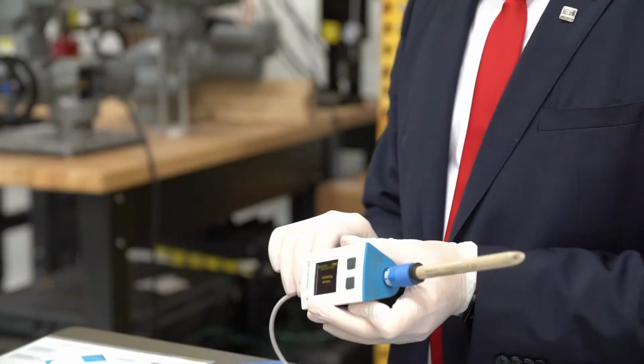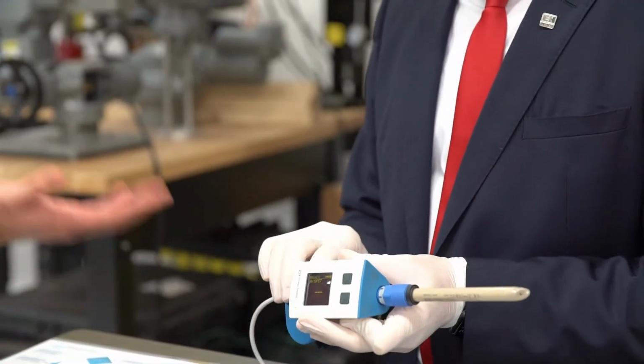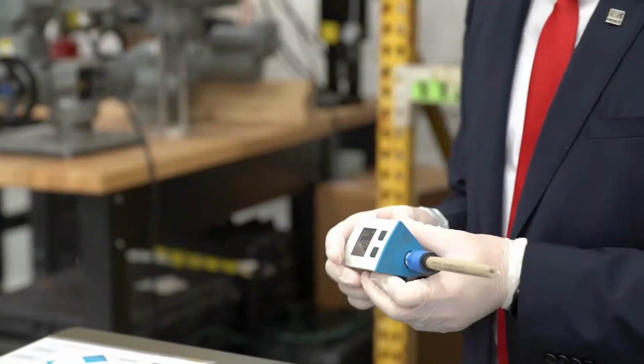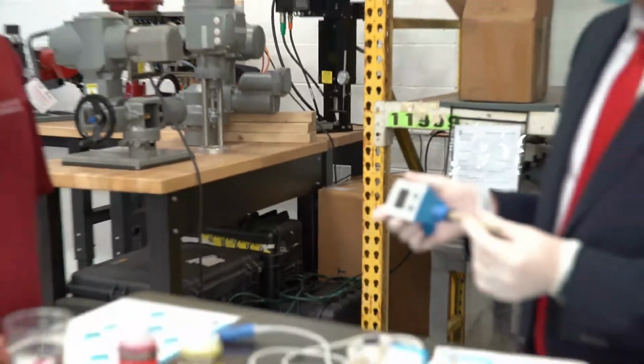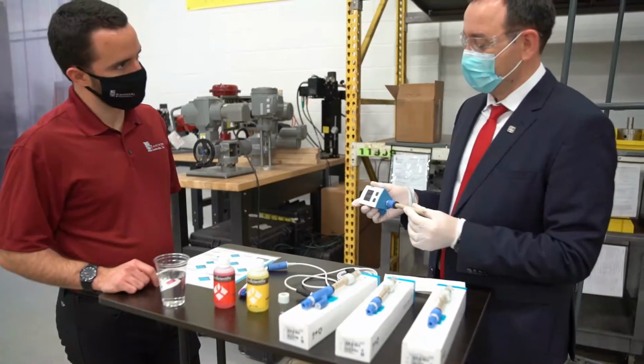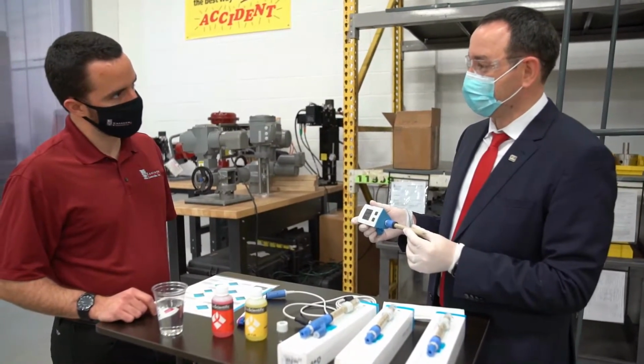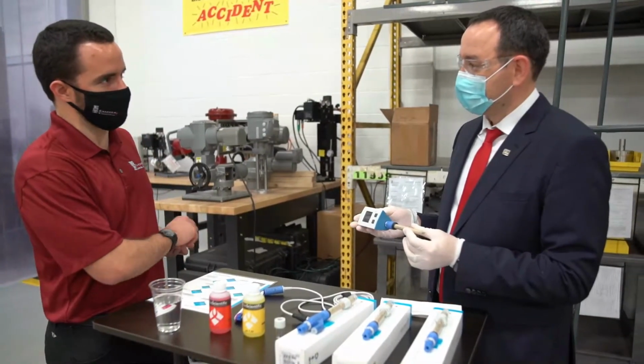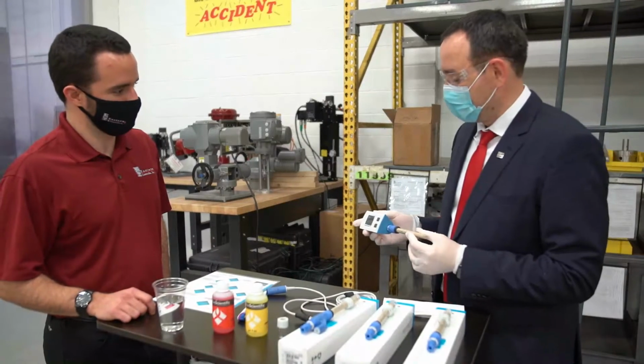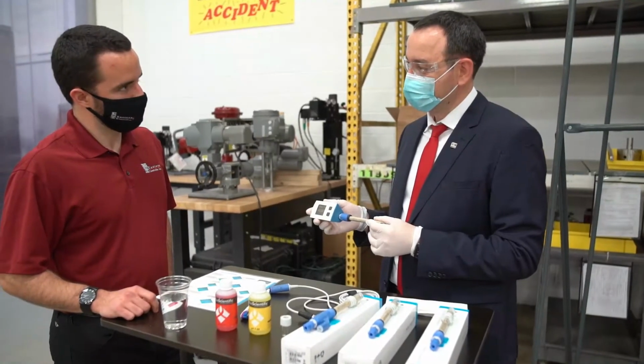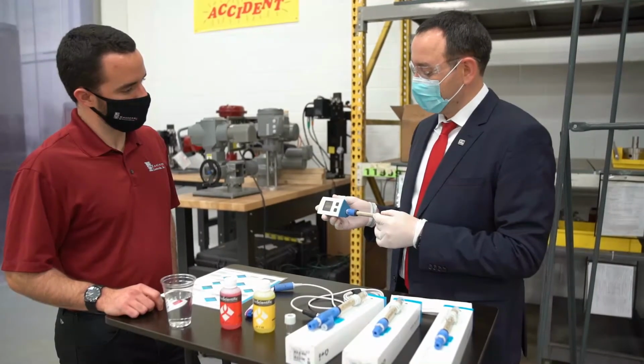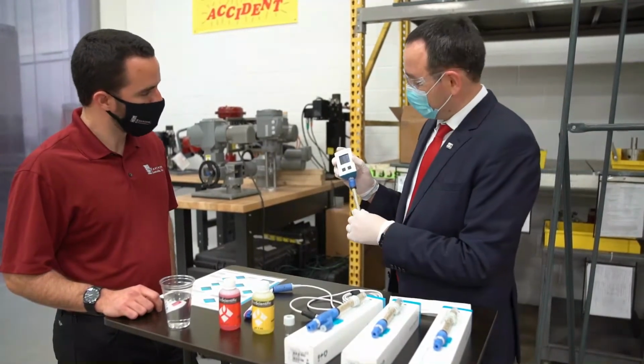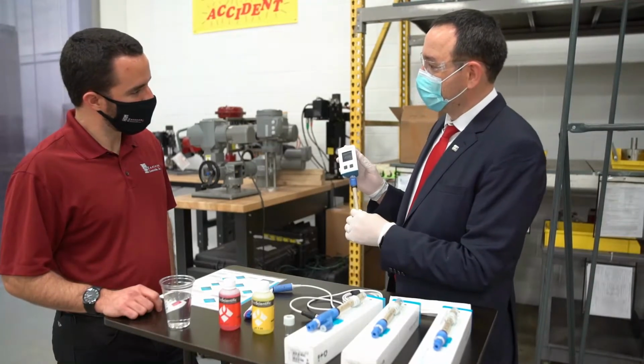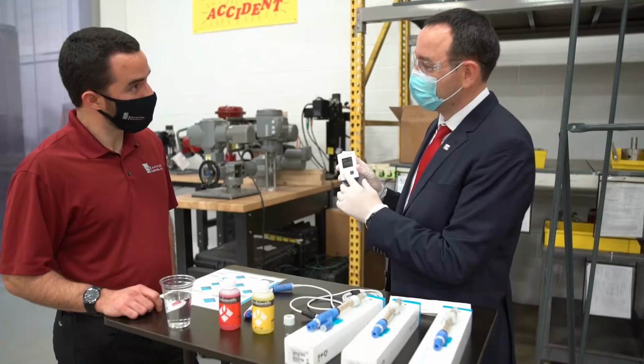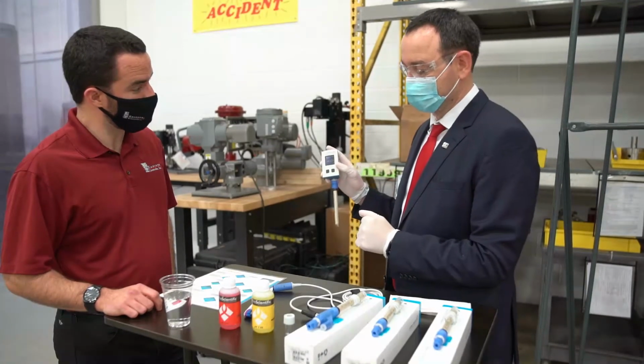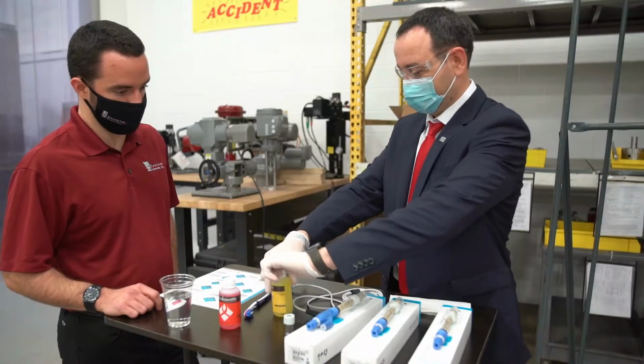So we don't need to use the cable then. Look at that. So what is this portable used for typically? This is used for the lab calibrations or measurements in the lab, or it can be used also for grab samples in the field. Walking around in the field doing samples. Correct. You can just have that in your pocket. And also it records the data either automatically or manual recording. It has a buffer inside, it has the memory, and every time we grab a sample, we can just simply hit a button and record the reading. That is amazing. Pretty much everything we can do with the Liquiline.